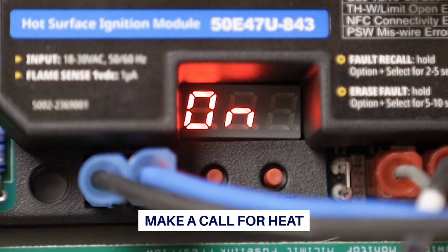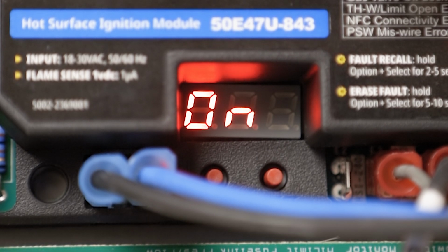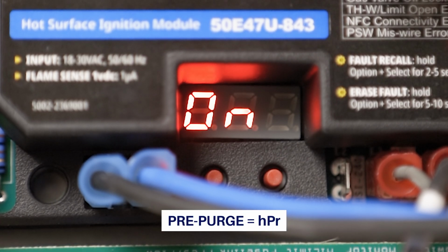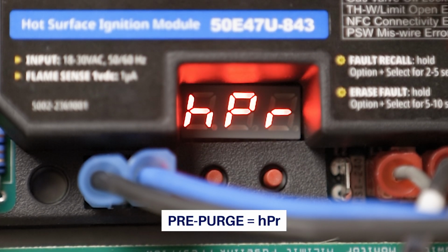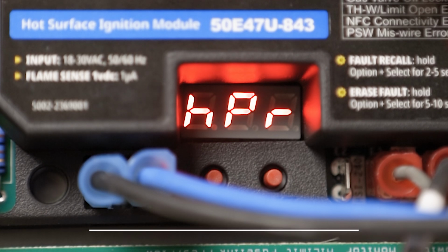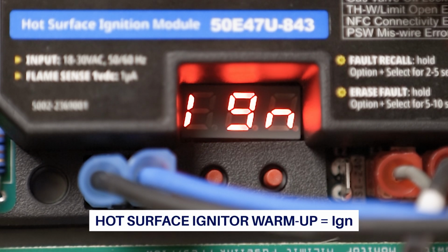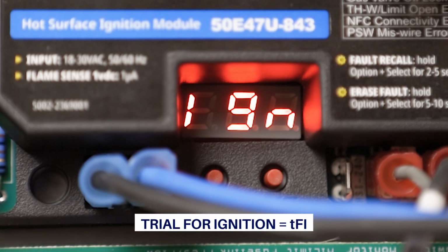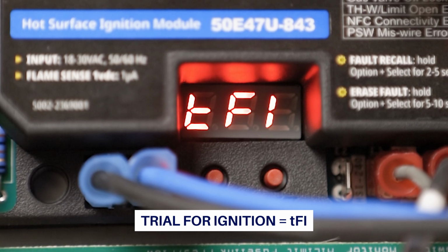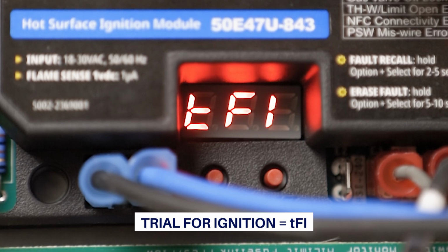To verify proper ignition, use the heater's control and make a call for heat. The digital display will show the status of operation. For this application, it will first display the letters HPR, indicating the pre-purge mode, then IGN during the igniter warm-up period, then T, F, and I, indicating it is in a trial for ignition period.